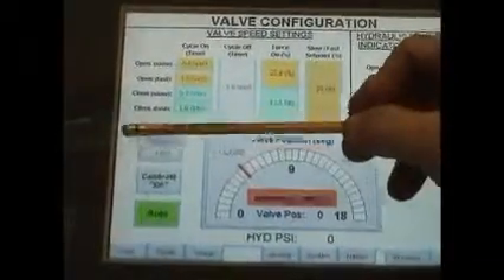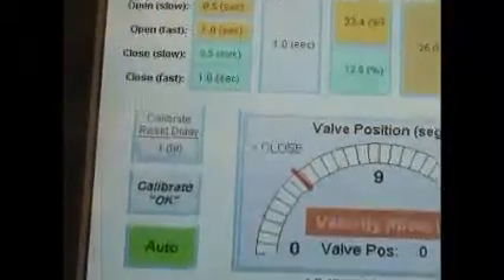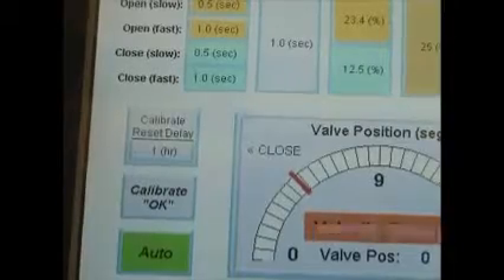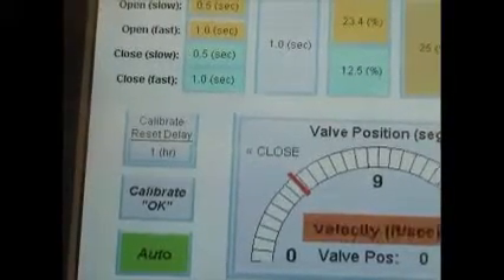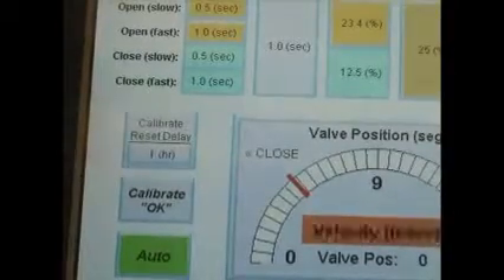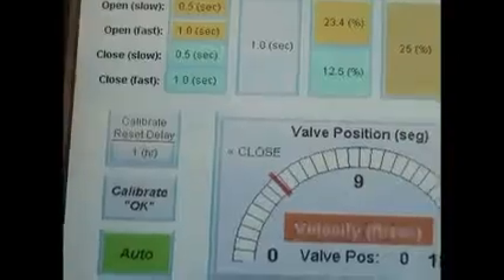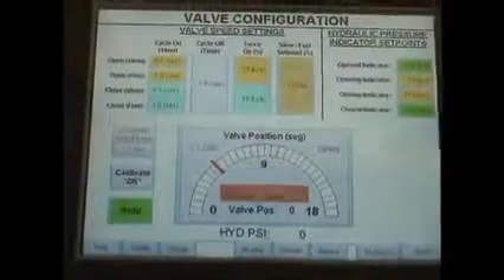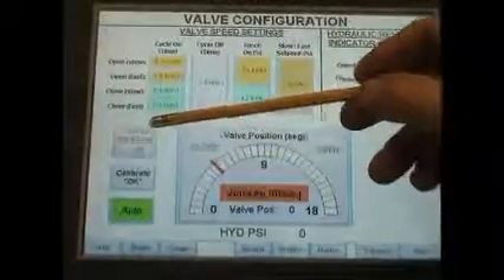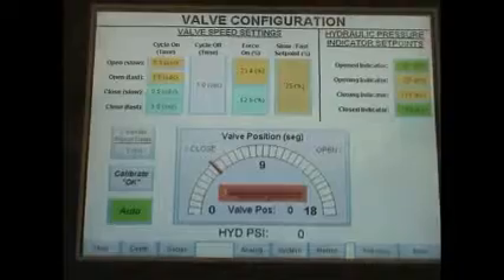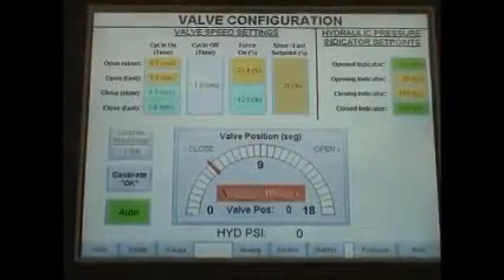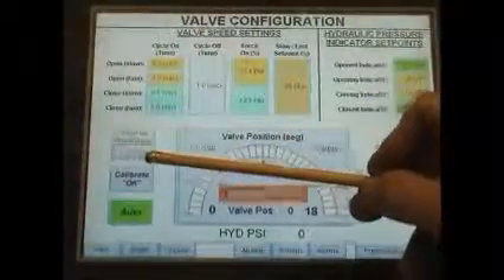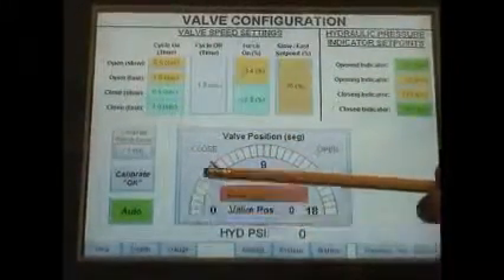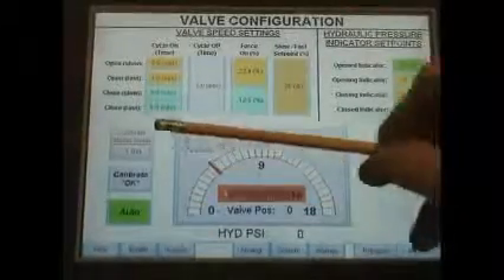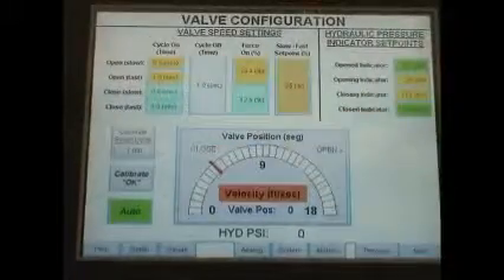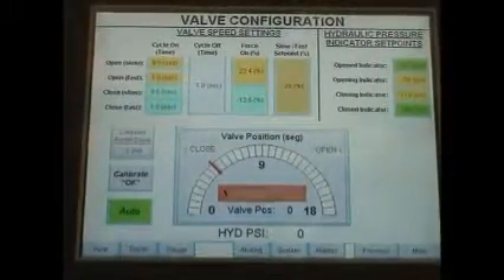The other thing we have is our calibration reset delay. We talked earlier about how the computer wants to calibrate due to any 30-degree temperature change. It will automatically go through a calibration. We also have the ability to set the calibration frequency here. For example, let's assume that our oil temperature is changing less than 30 degrees. The computer will automatically calibrate within 1 hour if the valve has not completely opened and completely closed during that hour period. It will want to calibrate within the 1 hour. Let's say, well, I don't want it to calibrate that frequently.